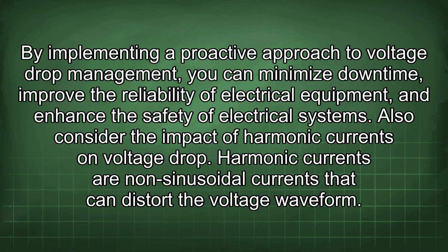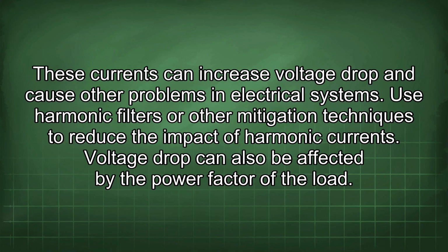Also consider the impact of harmonic currents on voltage drop. Harmonic currents are non-sinusoidal currents that can distort the voltage waveform. These currents can increase voltage drop and cause other problems in electrical systems. Use harmonic filters or other mitigation techniques to reduce the impact of harmonic currents.